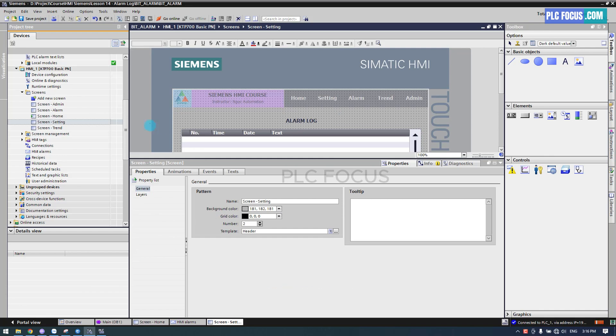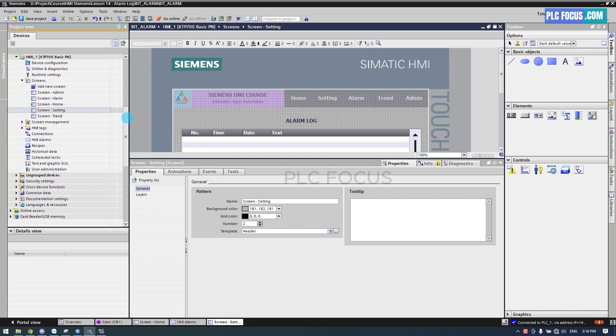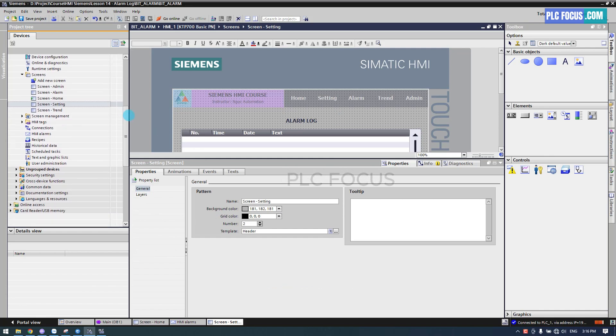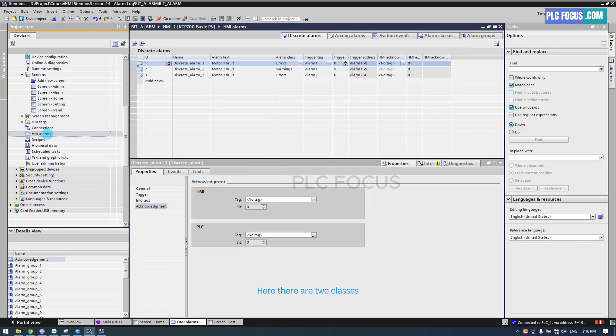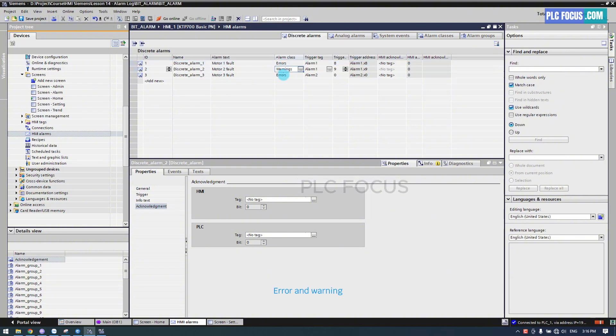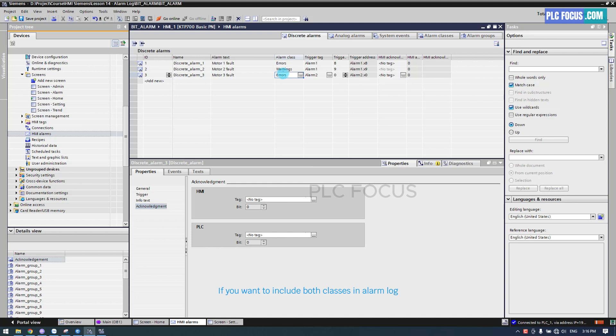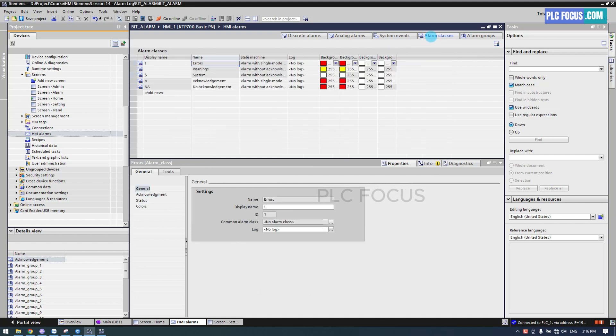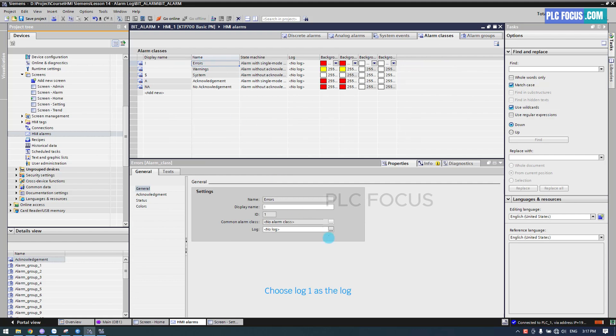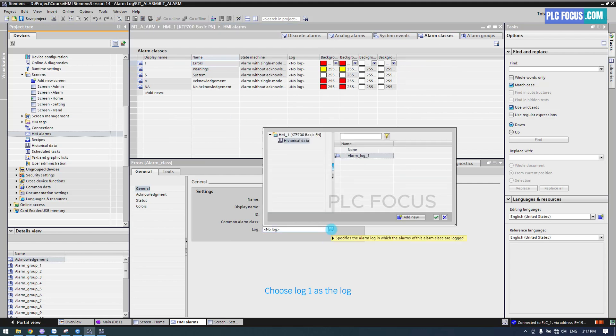One more step. Back to the Alarm HMI section. Here, there are two classes, Error and Warning. If you want to include both classes in Alarm Log, you need to select Alarm Class. Click on Error. Choose Log 1 as the log.